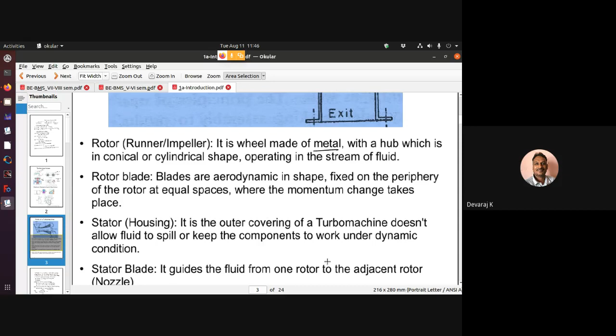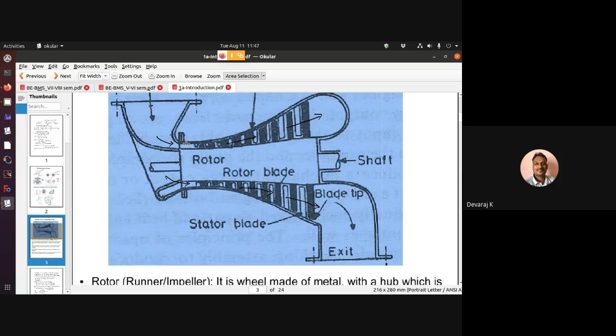Look at this particular thing. The fluid is coming like this. Maybe what I have is a stator, then a rotor, stator, rotor. So the stator vane guides the fluid. The first stator vane before the first rotor is called the inlet guide vane or IGV. There are machines where you may have more than one inlet guide vane, maybe two, so multiple inlet guide vanes can be there. In between, they are all called stator vanes. Guide vanes guide the fluid, and what comes near the inlet we call inlet guide vanes or IGVs.